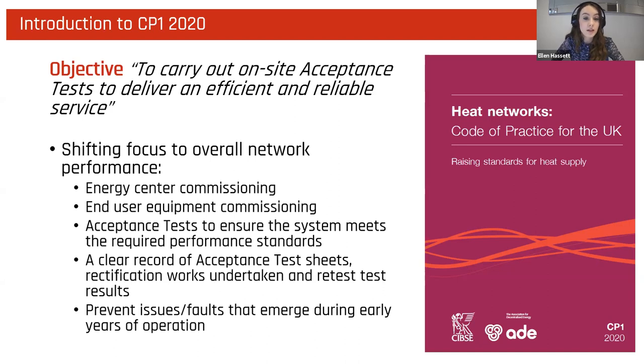In CP1 2020, there has been a shift in focus to overall network performance rather than performance of individual components during heat network commissioning. Poor commissioning and performance of the energy center is often associated with unstable flow temperatures. In the past, there's been a tendency during commissioning to solely focus on achieving stable operation during peak load, despite part load conditions being more common during operation. This oversight leads to unstable flow temperatures during part or varying loads, risking the reliability of the heat network.